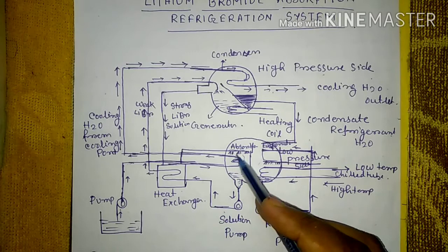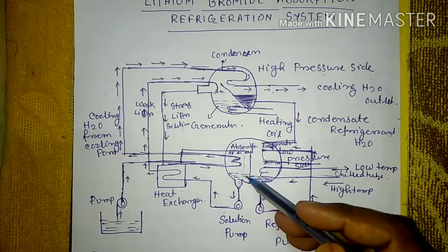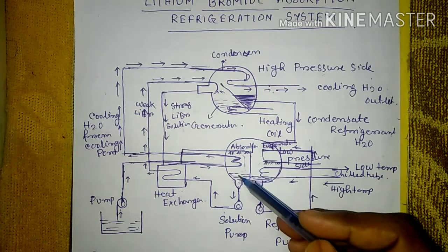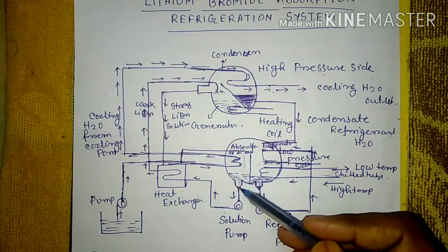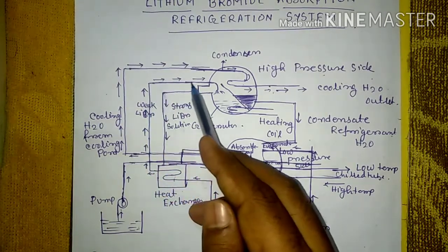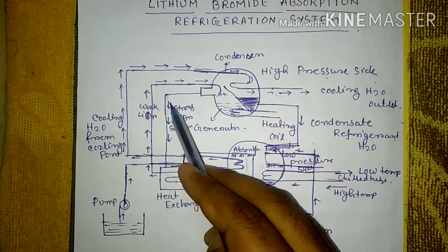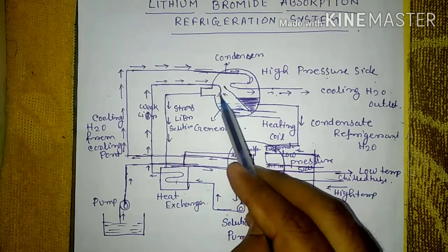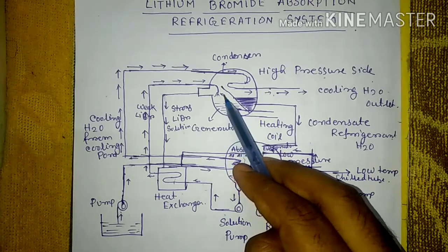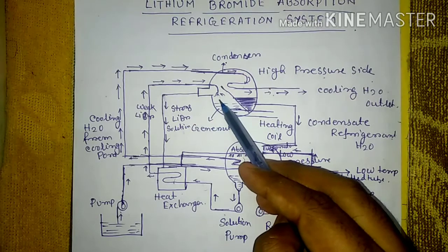In the absorber, liquid lithium bromide is sprayed and mixes with the incoming water vapor, forming a weak lithium bromide solution. This weak solution is then pumped via the solution pump through the heat exchanger to the generator, which contains a heating coil. The heating separates the water vapor from the lithium bromide.